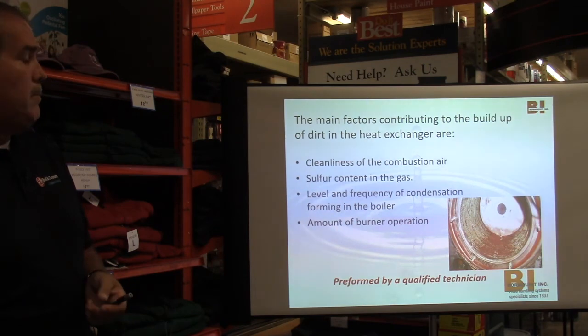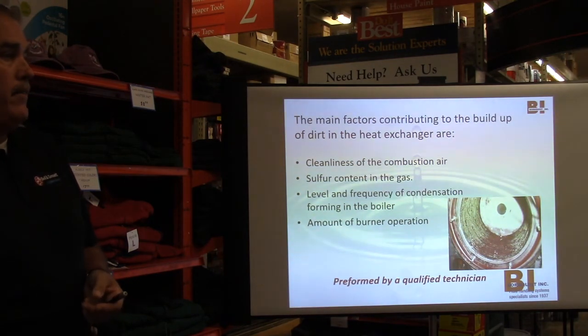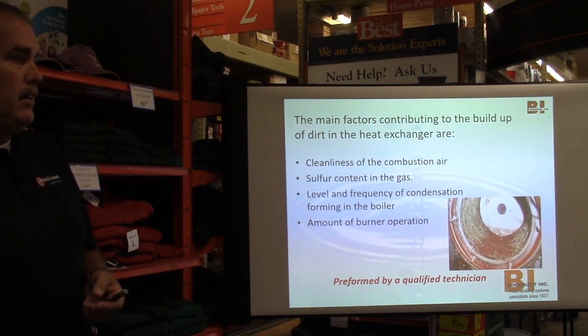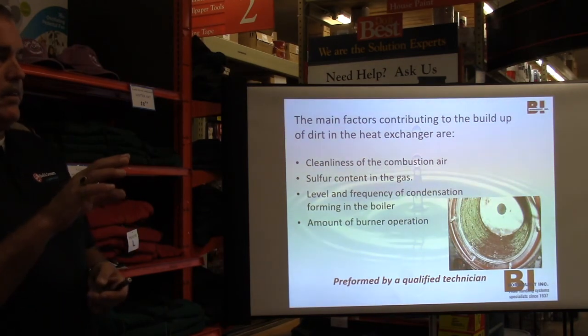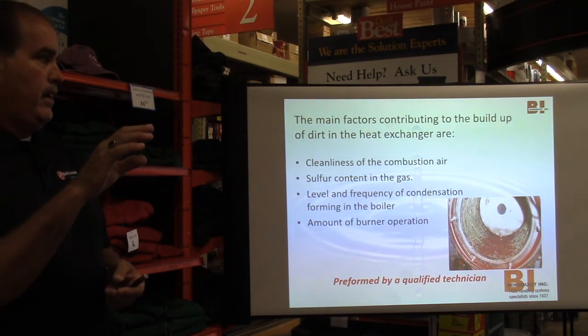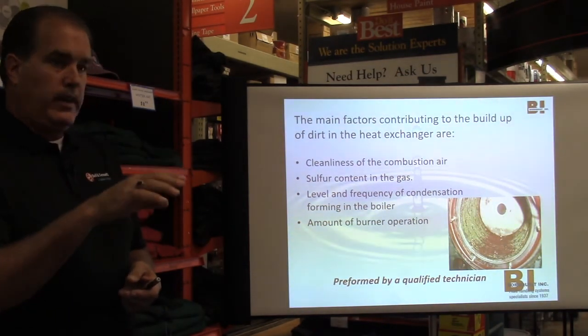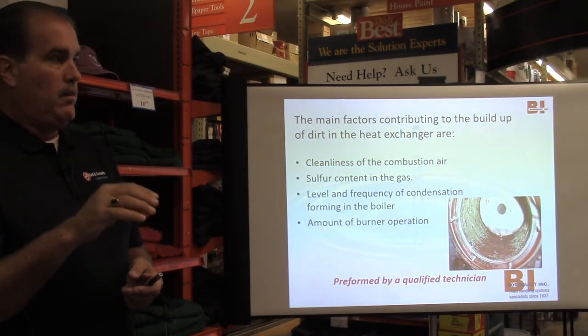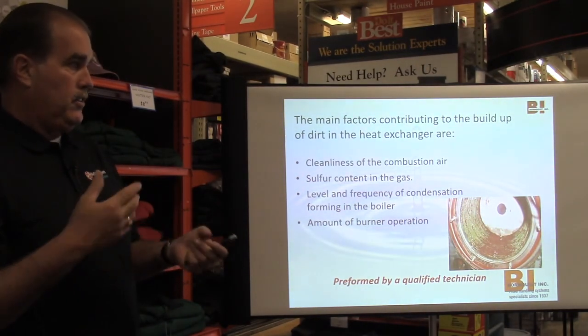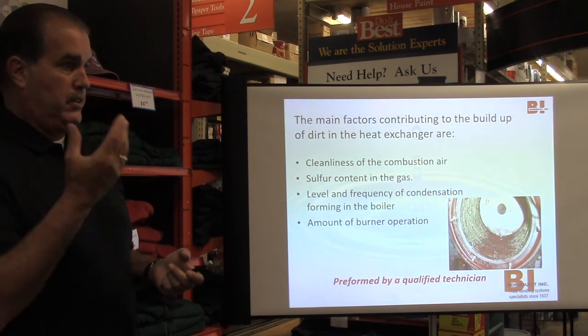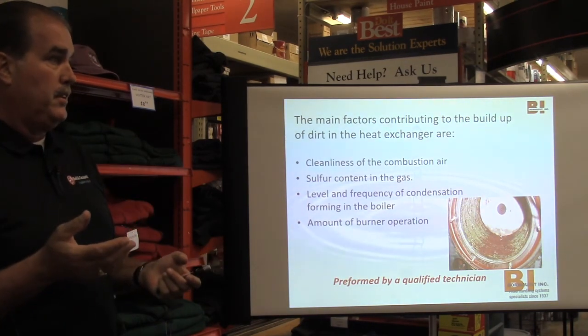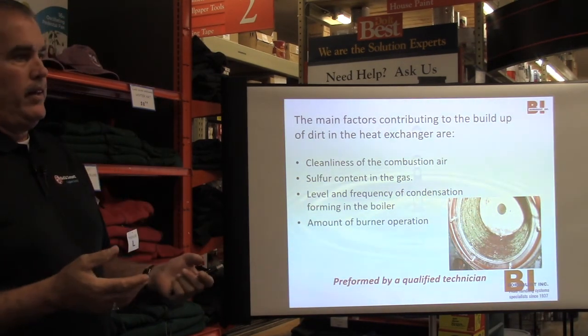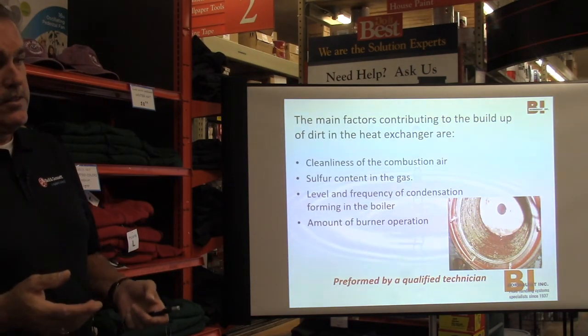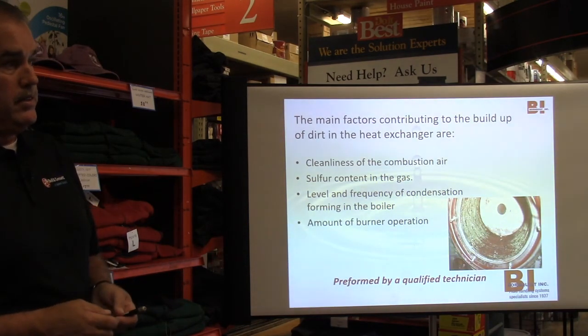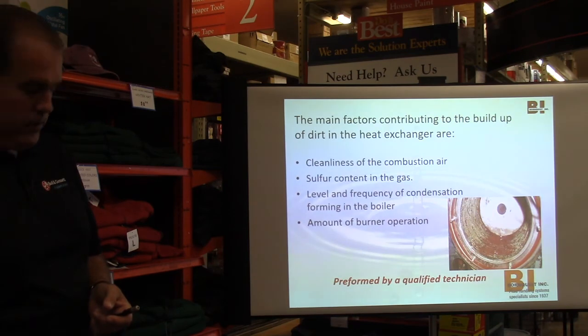One other thing about combustion air, you've got to be careful of what's in the air. Here again, this is more commercial, but if you have a pool, you don't want chlorine around that combustion air. You don't want to suck in chlorinated air. You can smell the chlorine, like a pool nearby. Not typically in a residential application. Refrigerants you've got to be careful of because they can be super corrosive to heat exchangers.